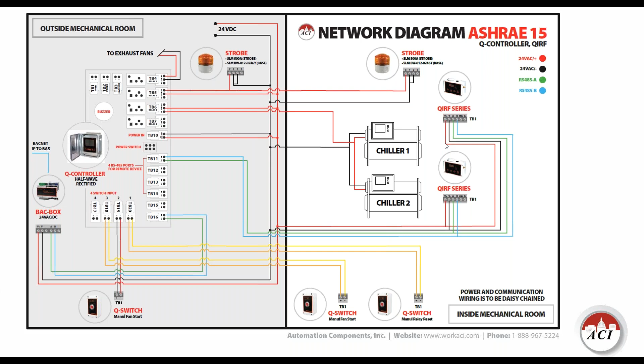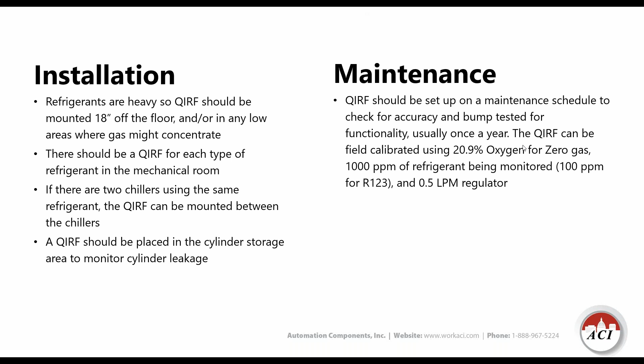Like I said, 18 inches above the floor. For QIRF field calibration, there's a test port on the side. We can set you up with the right Freon and the right test equipment to calibrate it if it's necessary. Like I said, there's a 13-year life on the sensor itself because it's infrared technology. And it's the same thing for the Freon system too.